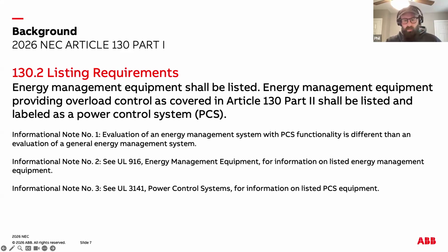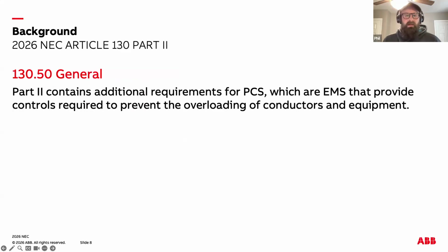The rest of Part 1 in Article 130 is basically a direct copy from the 23 version of the NEC. It details more shall and shall nots for what energy management systems can and can't do, like overriding alternate power sources for a healthcare facility or legally required standby systems, not stuff that we'll end up talking about too much. The first code in Part 2 of Article 130 defines a PCS as an EMS that prevents conductor and equipment overloading. Article 130, Part 2 goes on to describe requirements for PCS.